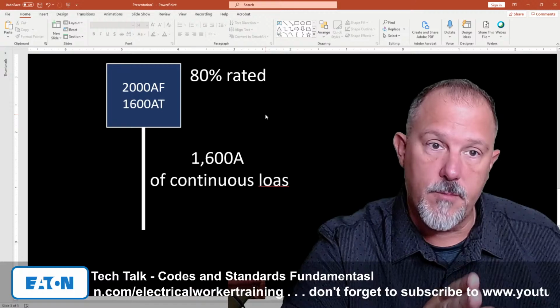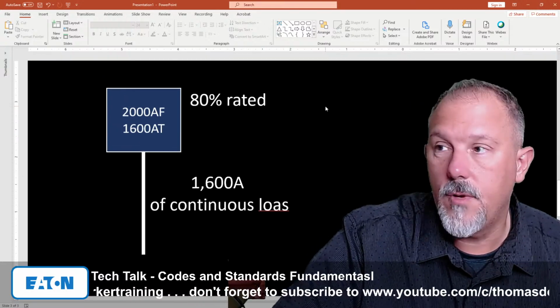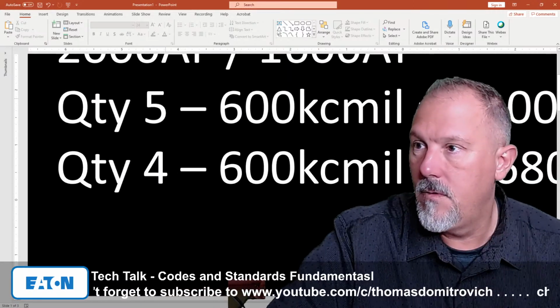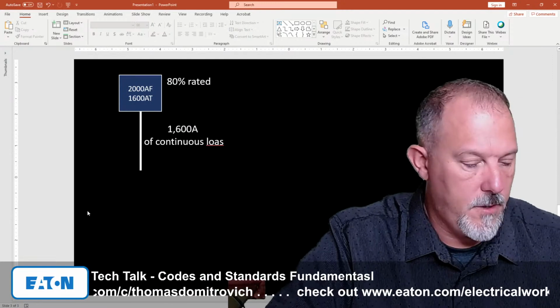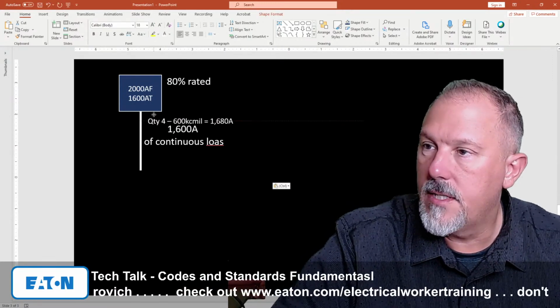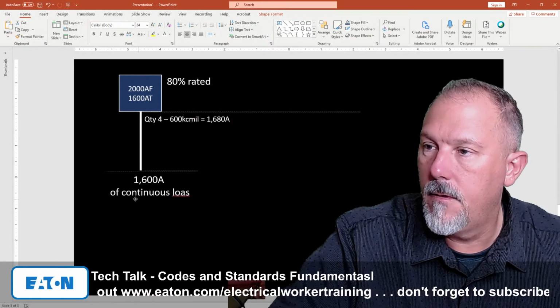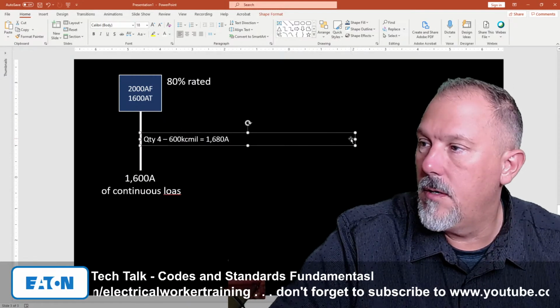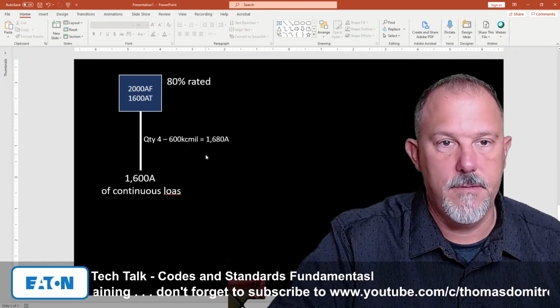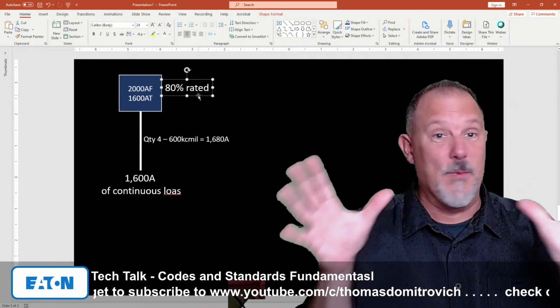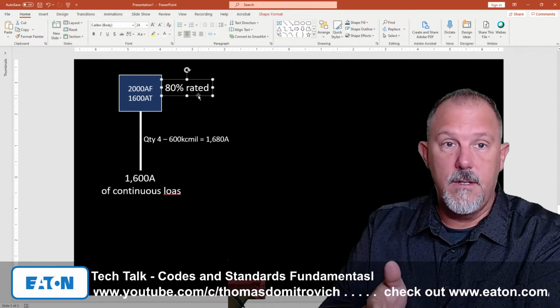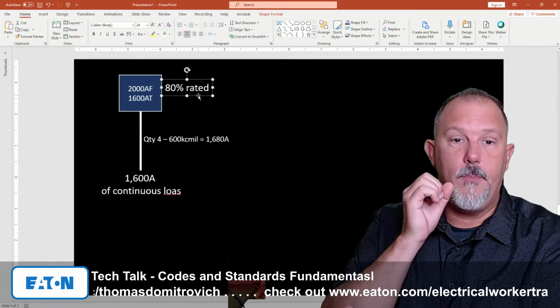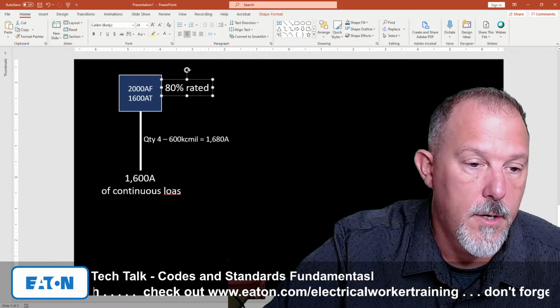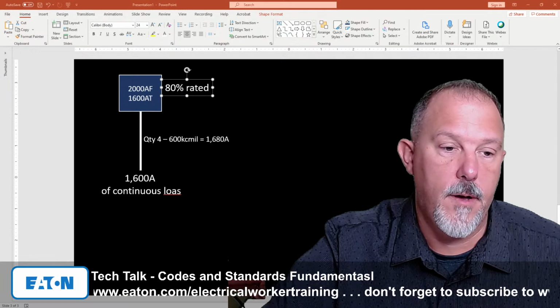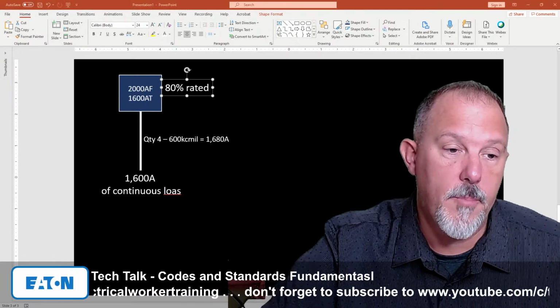I take a 2000 amp frame circuit breaker, and we're missing something here. Here's what we're missing. We're going to say quantity four 600 kcmil conductors, and this is an 80% rated breaker. This is what the question was right here. And they said, is this okay? Would I pass a field inspection or a plan review?